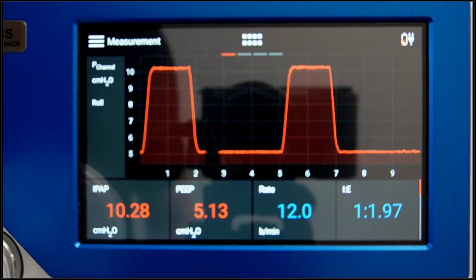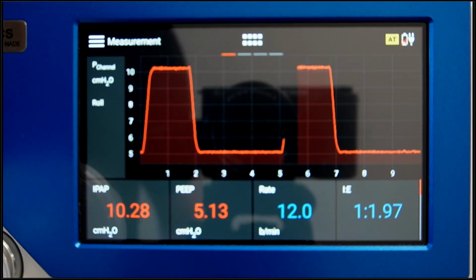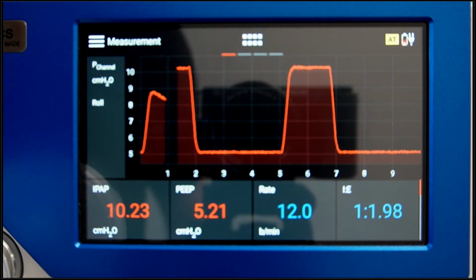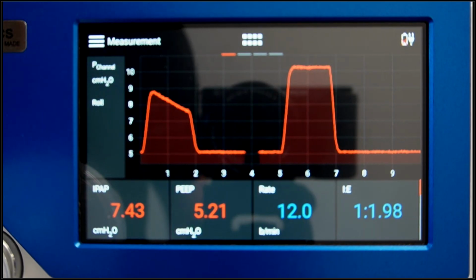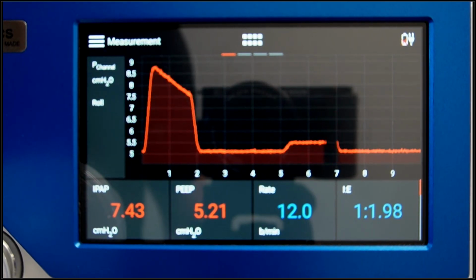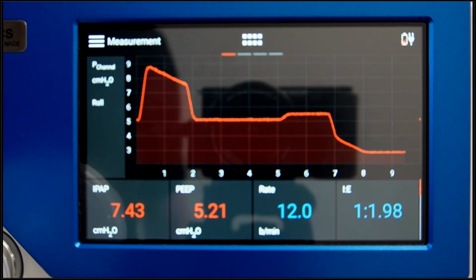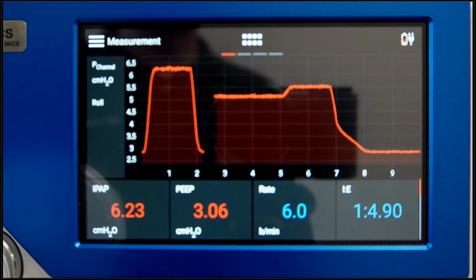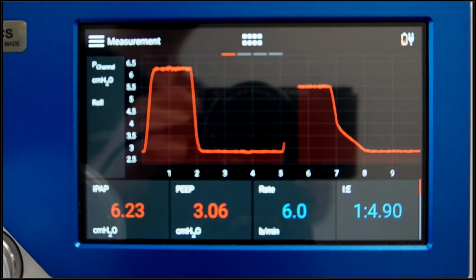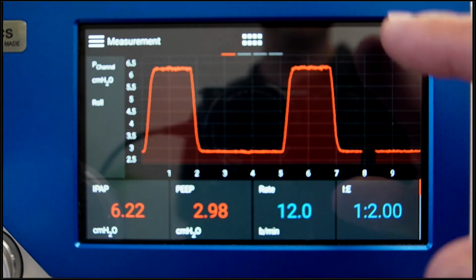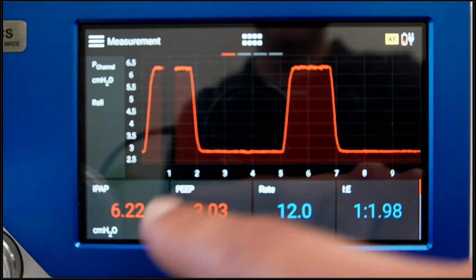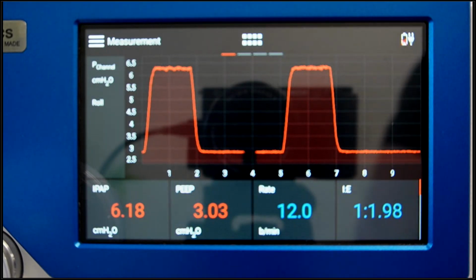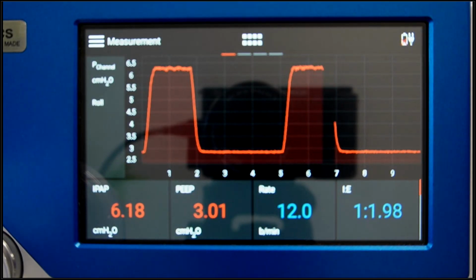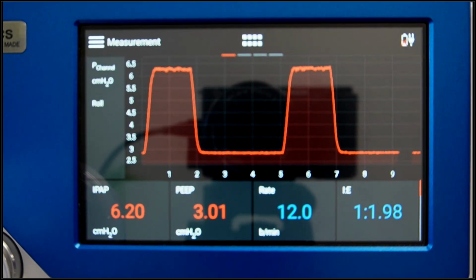And if I switch back to the previous settings we had with an IPAP of 6 and an EPAP of 3, you will see that once I apply these settings and the waveform changes, remember earlier, because we changed the settings of our ventilator, we had to amend our trigger settings, but now the device has done that automatically. So it's still triggering, and you can see we have accurate readings of our breath-based parameters here. So this is extremely helpful in situations that you have to find your own trigger settings.